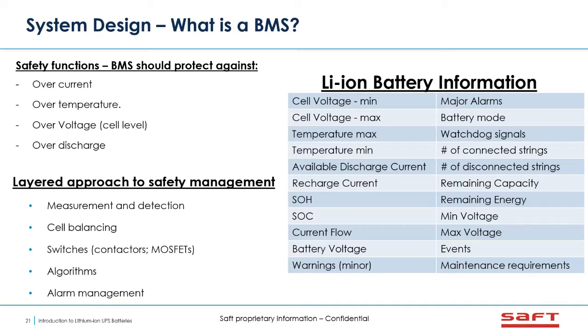But how we do that is through measurement and detection devices. It also performs cell balancing. We have switches, contactors, circuit breakers, MOSFETs inside the system, all safety algorithms that look at all the information going on and computing calculations like state of health or state of charge. The alarm management, so how the alarms are raised to the customer, all that incorporates a layered approach of safety through the BMS. And then on the right side of this slide, what we're looking at here is some of the information that you can get from the BMS.